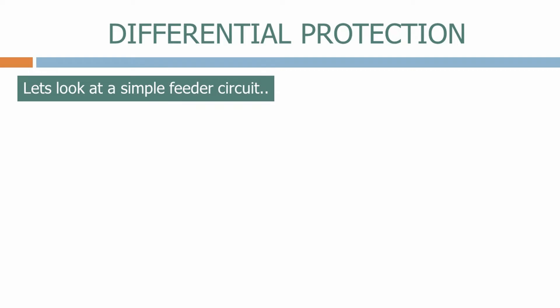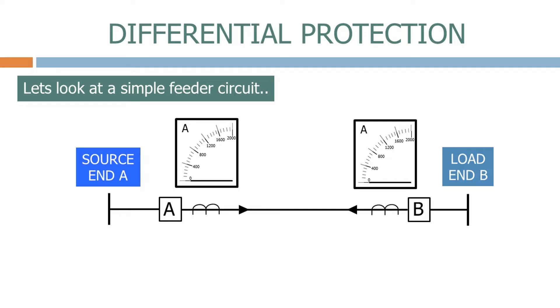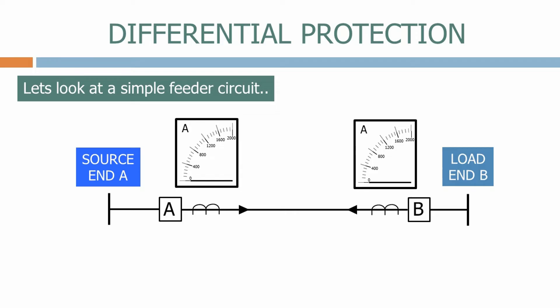Let's look at a simple feeder circuit. Here we have a feeder circuit with End A, which is the source of the power, and End B, which is the load. We therefore assume that power will flow from End A through the feeder and onto End B. To monitor the feeder, the differential feeder protection needs to compare the currents flowing through ends A and B.